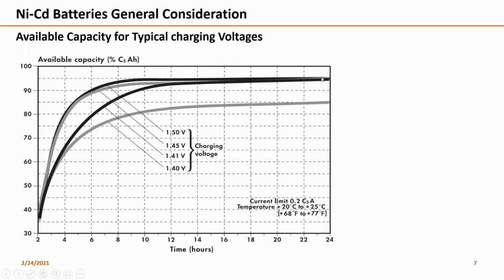But generally at industries, they will operate the battery range from 80 to 40, meaning we will be consuming only 40% of the battery. In some cases - the cell voltage of nickel cadmium is 1.2 - manufacturers prefer to discharge the cell till 1 volt. So that is a factor. Generally in a 220 volt DC system, we would have 243 volt or even 265 volt as additional voltage to have some cushion on the battery discharge.